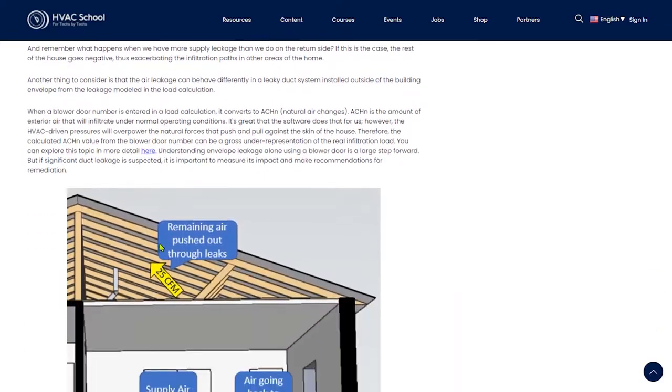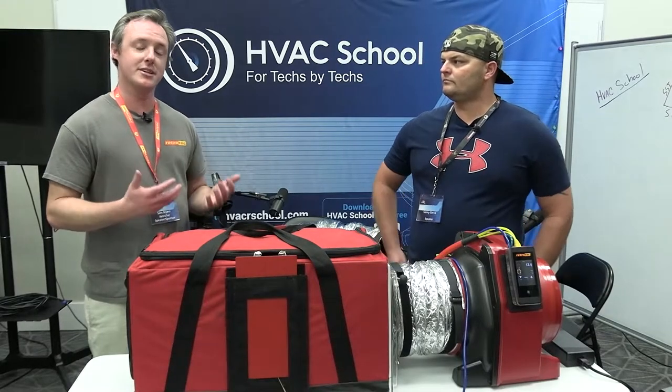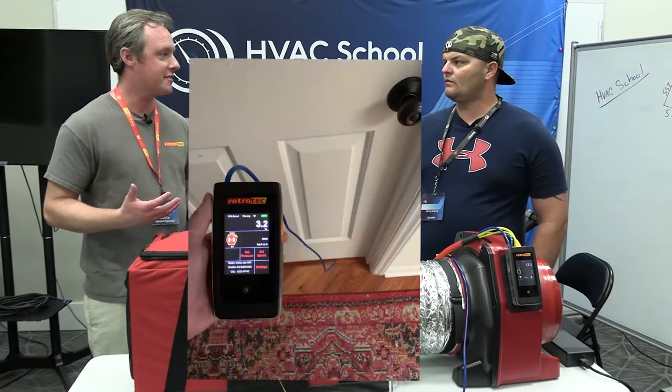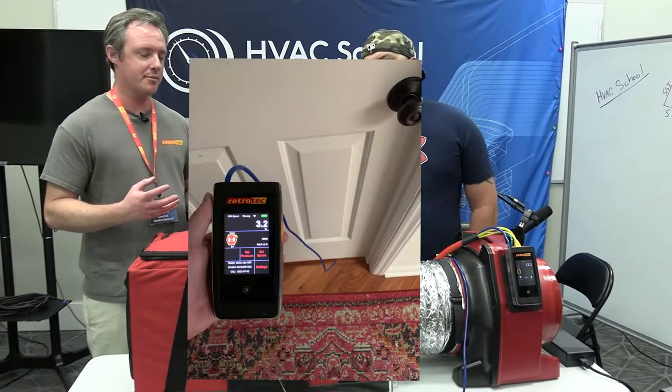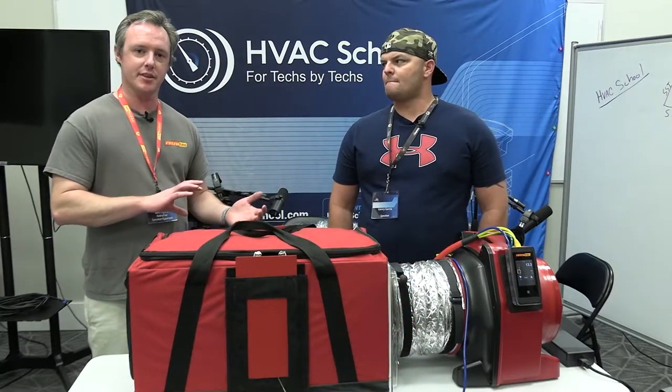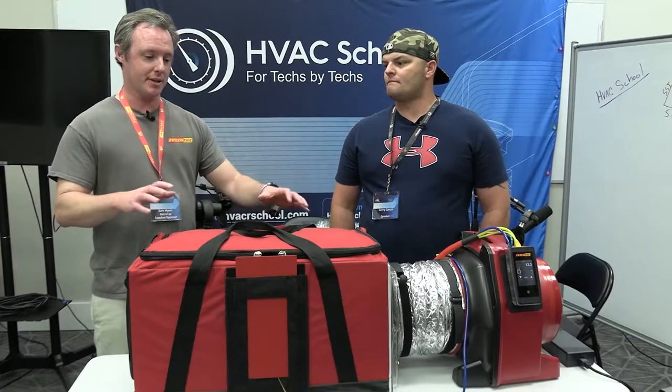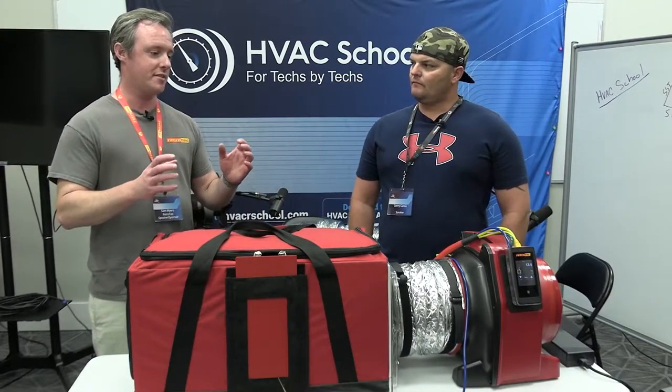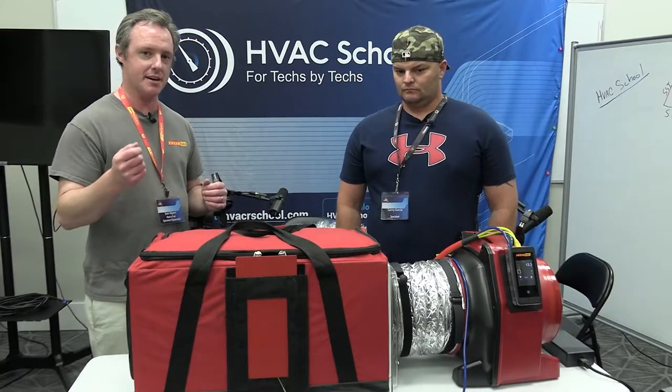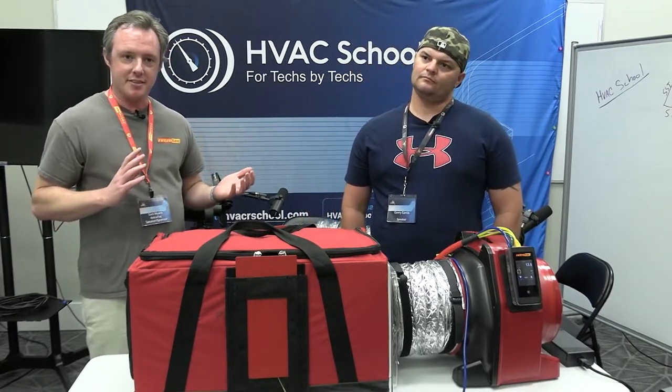Essentially what we're trying to do — the measurement that we take — is basically checking the balance of the house. What we're really looking for is making sure that any supply air delivered to a room, let's say a bedroom we have simulated here, if that bedroom door is closed, we still want a way to have that supply air get back to the return. In a lot of cases when we have that bedroom door shut, if we don't have a transfer grill, a jumper duct, or an individual return in that room, that room can over-pressurize and that air has to go somewhere. It usually gets pushed outside of the envelope, so any leakage in that room gets exaggerated by the HVAC system.